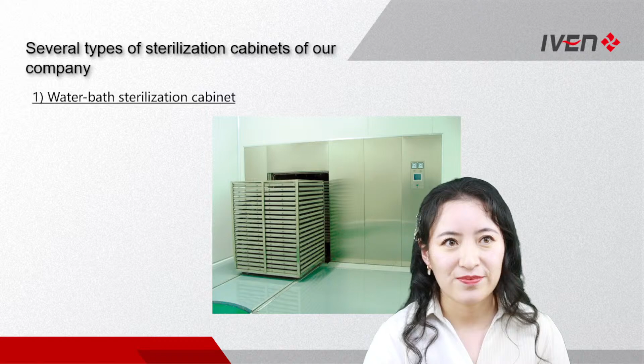So here we have several types of sterilizers from our company for you. First one is the water-bath sterilization cabinet. Here I will introduce our sterilizers like this: first the principle, then the products which can be used in the sterilizer. For this type, the principle: overheated circulating water is used as the sterilization heating carrier to perform water spray sterilization operations on items. And in the whole working process, the superheated water runs in a relatively closed circulation system.